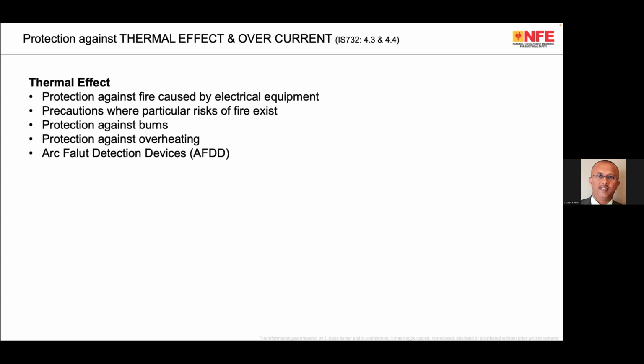Now, coming to the point, protection against thermal effect. There are two major subjects. The first is protection against thermal effect itself. Here the subjects to be discussed are protection against fire caused by electrical equipment, meaning the equipment catching fire, how this is handled in the standard and in a product; precautions where particular risk of fire exists, that means in a location where the risk of fire is higher, what to do in that case; protection against burns, protection against overheating, and the arc fault detection device. Of course, AFDD is a part of protection against fire caused by electrical equipment. So these are the measures which protect against the thermal effect.